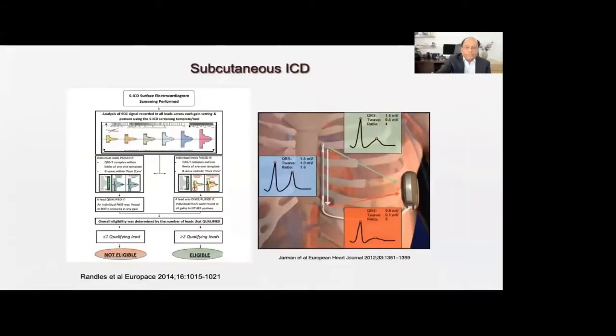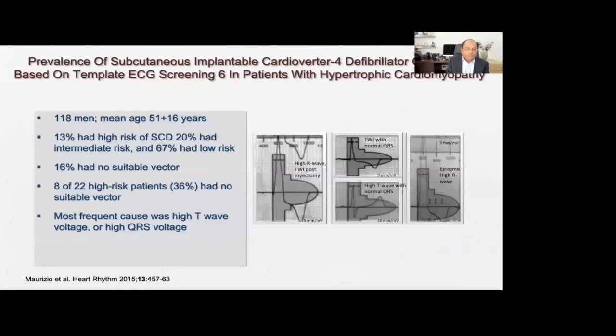The important point here is that all patients are not suitable for subcutaneous ICD. So we have to do a screening of the surface ECG before a patient can be accepted for subcutaneous ICD. This was initially done using a plastic scale-like tool, but now it is done in an automated fashion using a programmer. Certain patients may have a very tall T wave, and that may lead to double counting. So we have to have certain QRS configuration and T wave; there are certain limits to QRS and T wave. What we have seen is that about 8 to 10% of patients may be rejected based on the surface ECG, and this percentage may be higher in patients with hypertrophic cardiomyopathy. The most frequent cause is a very tall or deep T wave.